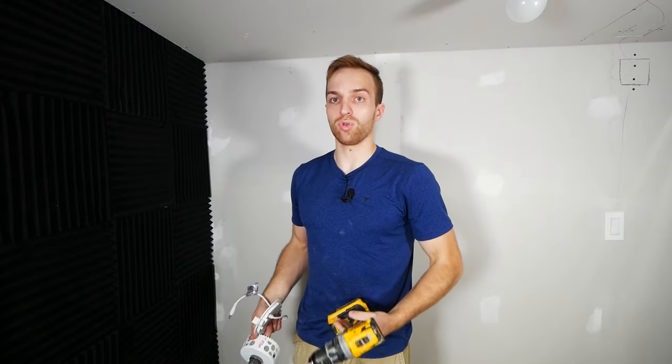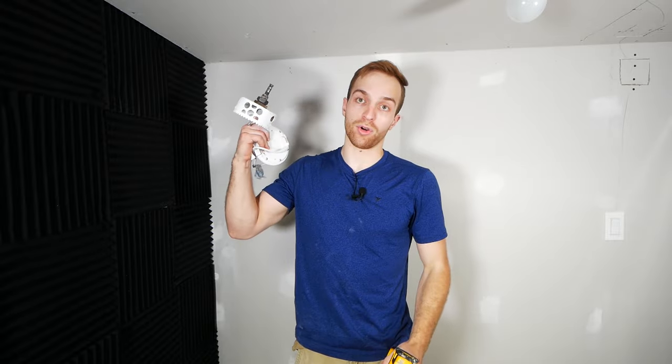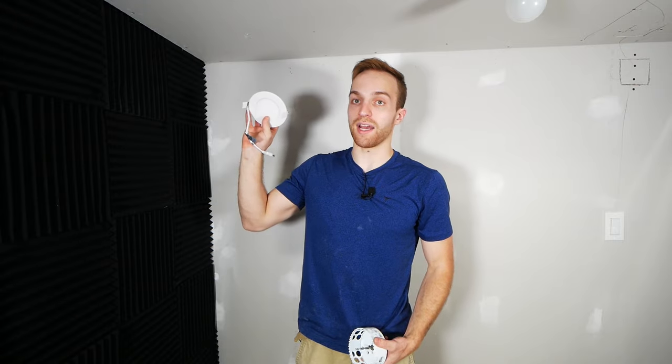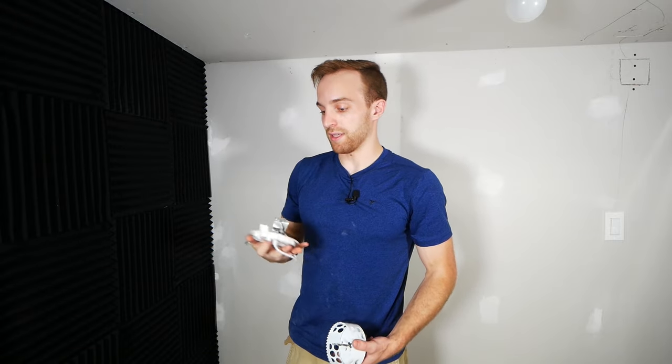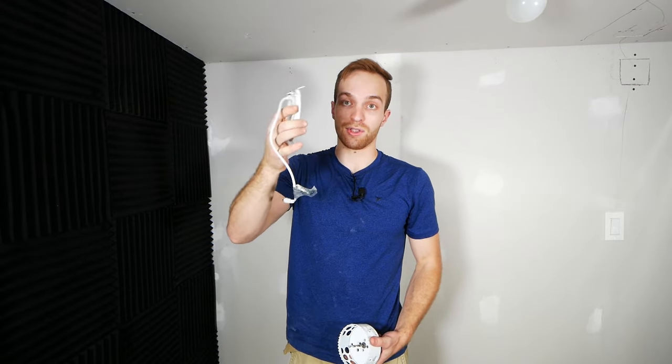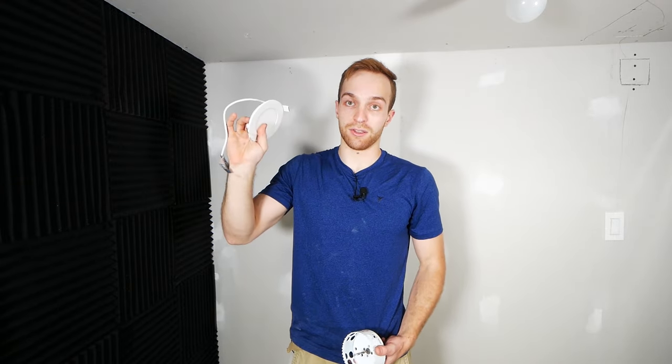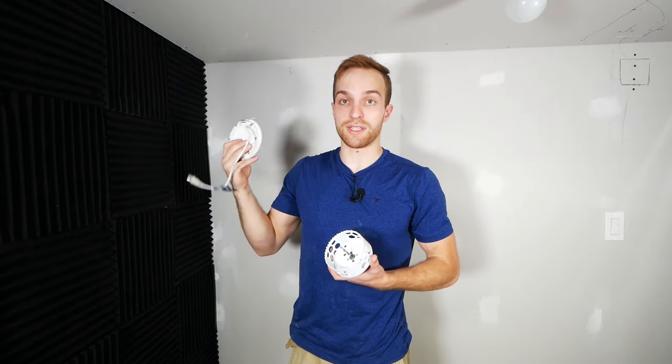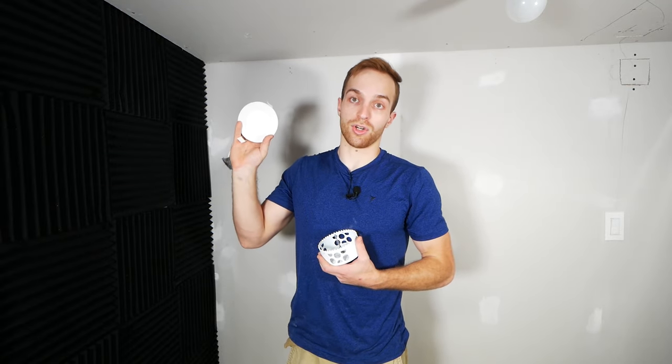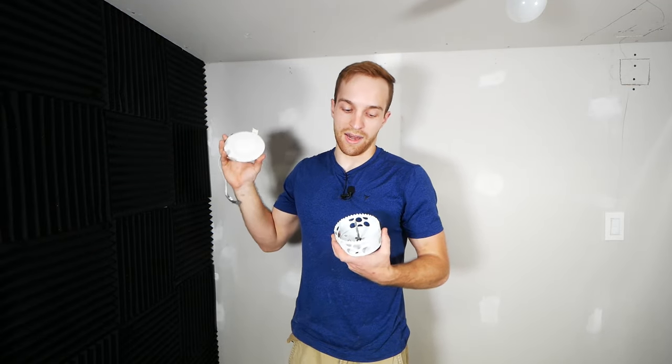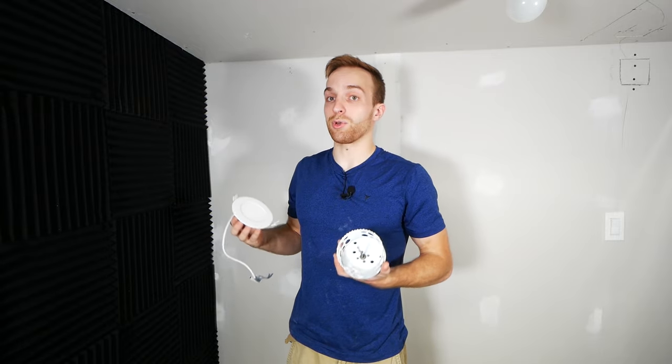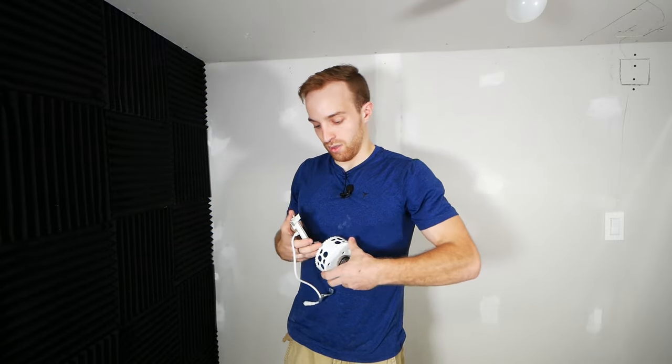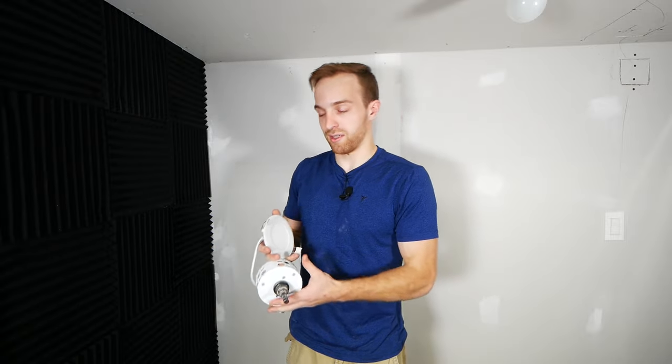To make the holes here, I'm going to be using a drill with a 4 1/4 inch hole saw. Now, your hole size may vary depending on what brand and size of pot lights you go with. The style I'm using here is the wafer style. It's very thin. It's going to make for an easy install. LED. And to determine the size of hole that you'll need, most of them will come with instructions that will give you a hole size. And in saying that, you don't need necessarily to use the exact dimension that they give you, although that would work best.